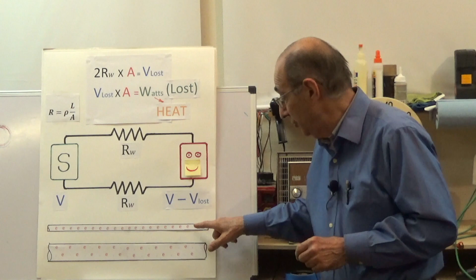So I've got a piece of wire here, this thin one, and I start pushing amps through there. If I push a lot through there, I'm going to produce a lot of heat, and pretty soon it can't dissipate enough heat. It's going to get so hot that it will melt the insulation, or it might get to the point where it can ignite combustible materials. Now, there's certain circumstances where it's okay for it to get hot, but those are very limited examples.